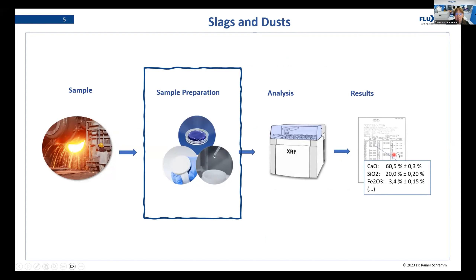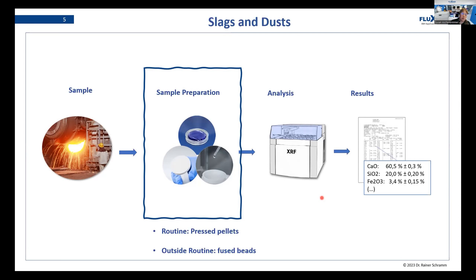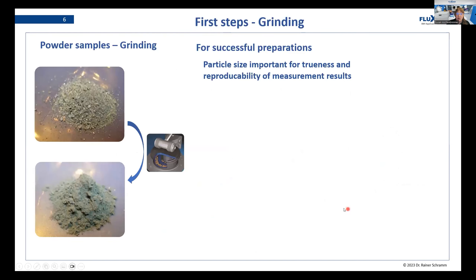Now we will have a look at sample preparation — how we can prepare these slags and filter dusts. For routine slag preparation, it is most of the time pressed pellets. When you are in your routine and have to analyze slags on a regular basis, it will be pressed pellets in most cases. But if your slags show different values outside of your routine that you are not expecting, fused beads might be a good idea.